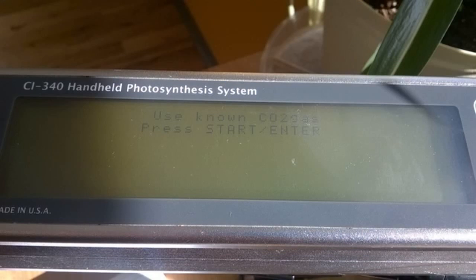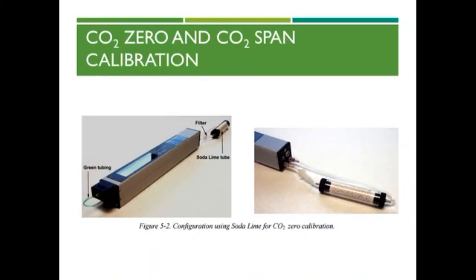Therefore, if the gas isn't 0 ppm or hasn't been allowed enough time to run through and completely clear the system, the calibration can skew the instrument further. After the CO2 0 is set, the instrument will display Use Known CO2 Gas. Press Start Enter. If you wish to calibrate the CO2 span, hit Start Enter. If you only wish to zero the CO2 sensor, press Exit.